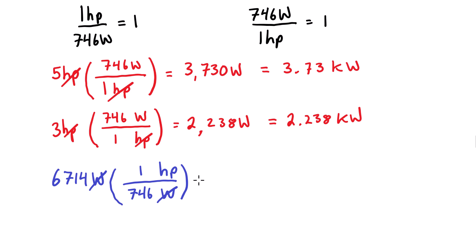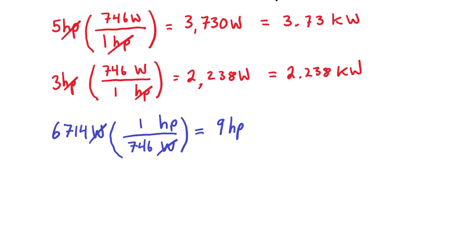So our watts are going to cancel out. Basically, we're just going to divide the watts by 746 to get horsepower—you can do it that way if that makes more sense. Basically, 6,714 divided by 746 gives us 9 horsepower.